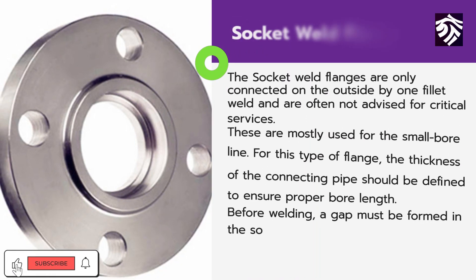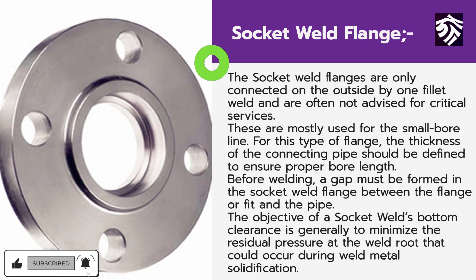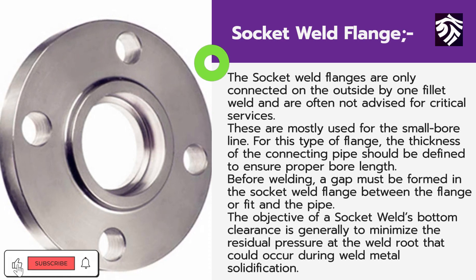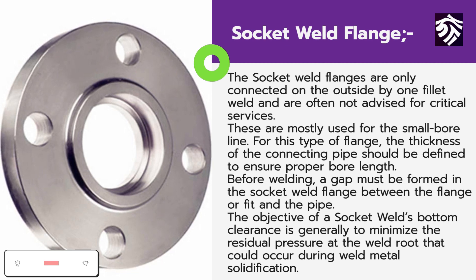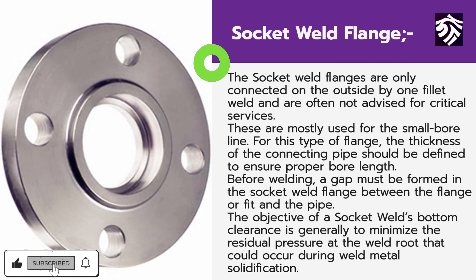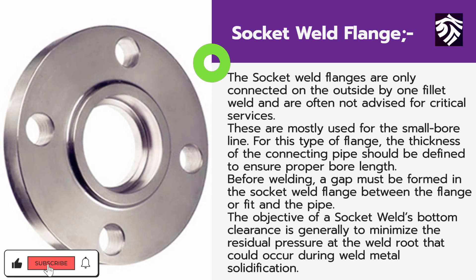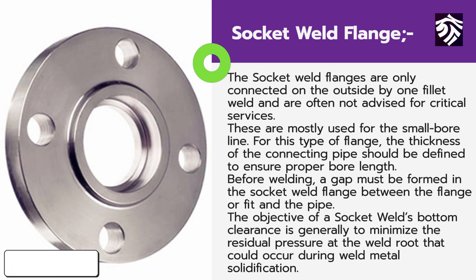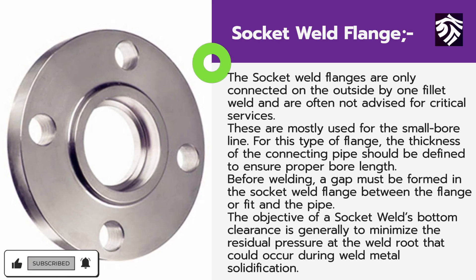Another common type of flange is the socket weld flange. Socket weld flanges are only connected on the outside by one fillet weld and are often not advised for critical services. These are mostly used for small bore lines. For this type of flange, the thickness of the connecting pipe should be defined to ensure proper bore length. Before welding, a gap must be formed in the socket weld flange between the flange and the pipe. The objective of the socket weld bottom clearance is to minimize residual pressure at the weld root that could occur during weld metal solidification.